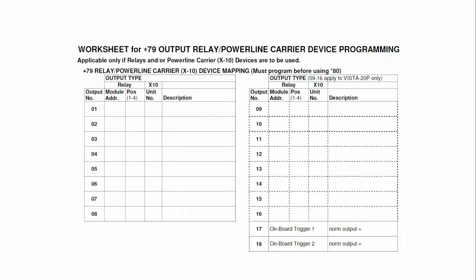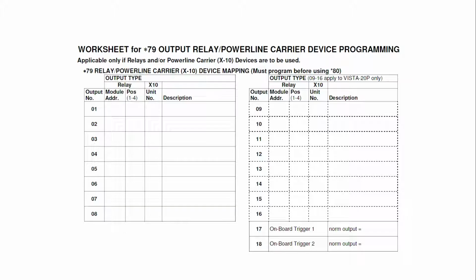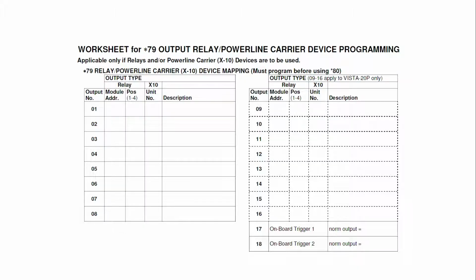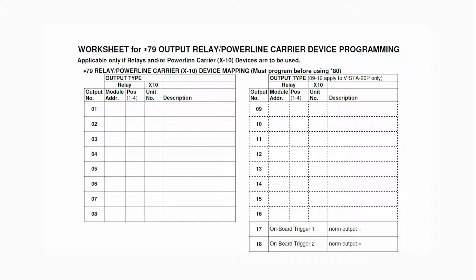Press star to move forward. Next, enter your output type. For relay modules, the output type is 1. Press star. You will then need to enter the 4204's address based on the dip settings. Press star. Lastly, enter the relay position 1 through 4. Press star to save this relay's configuration. After you have enabled all outputs needed, enter 00 star when asked to enter an output number.